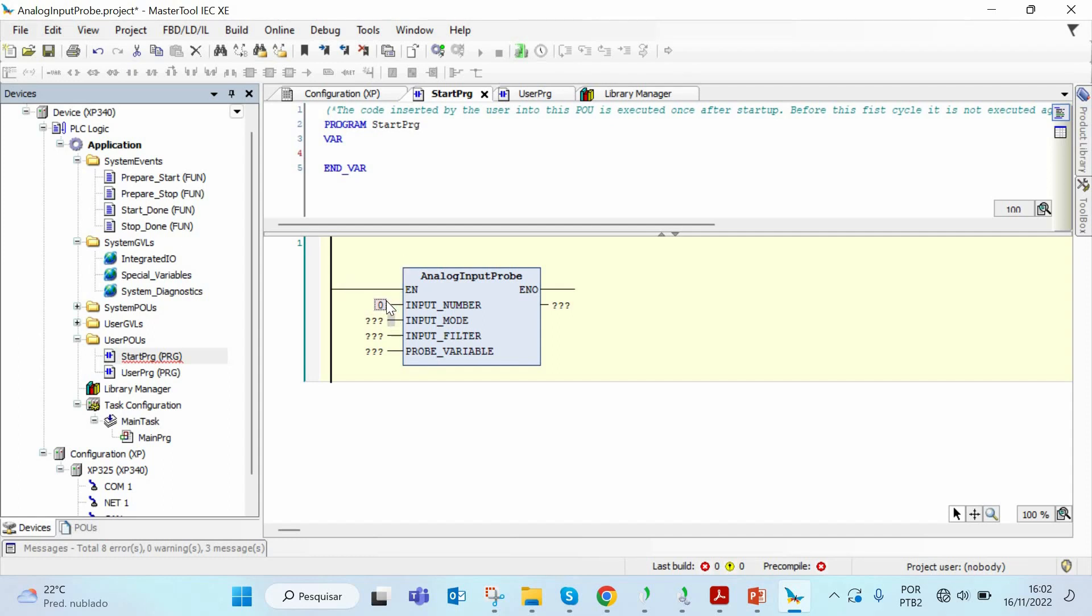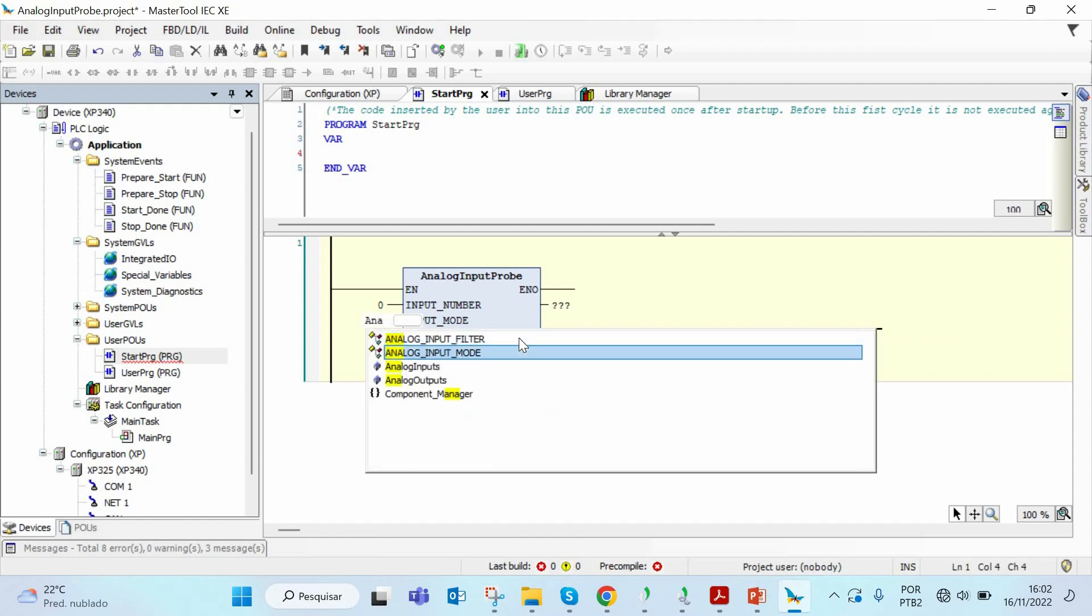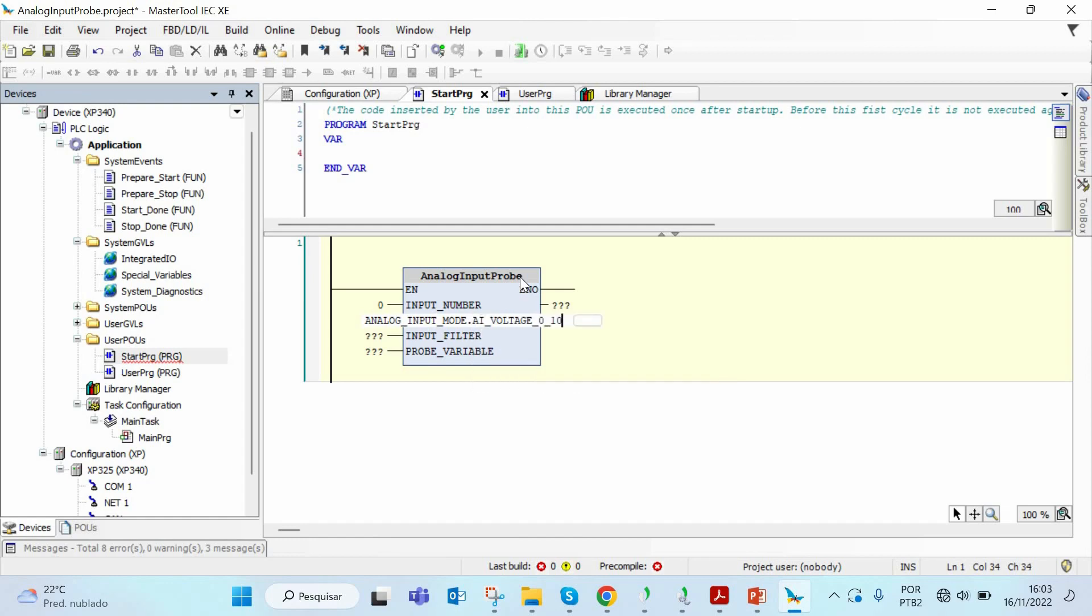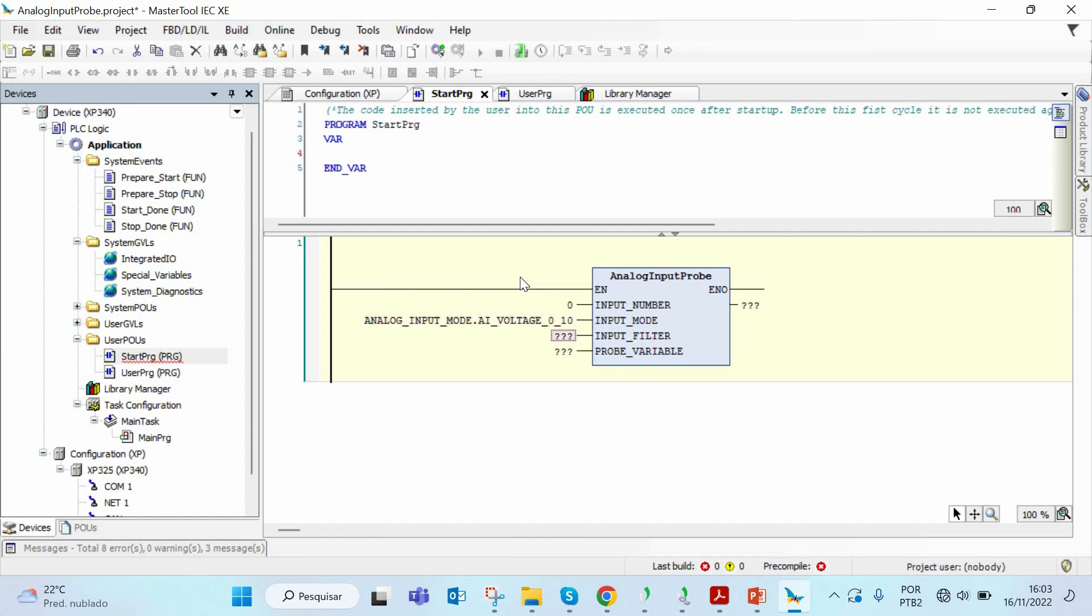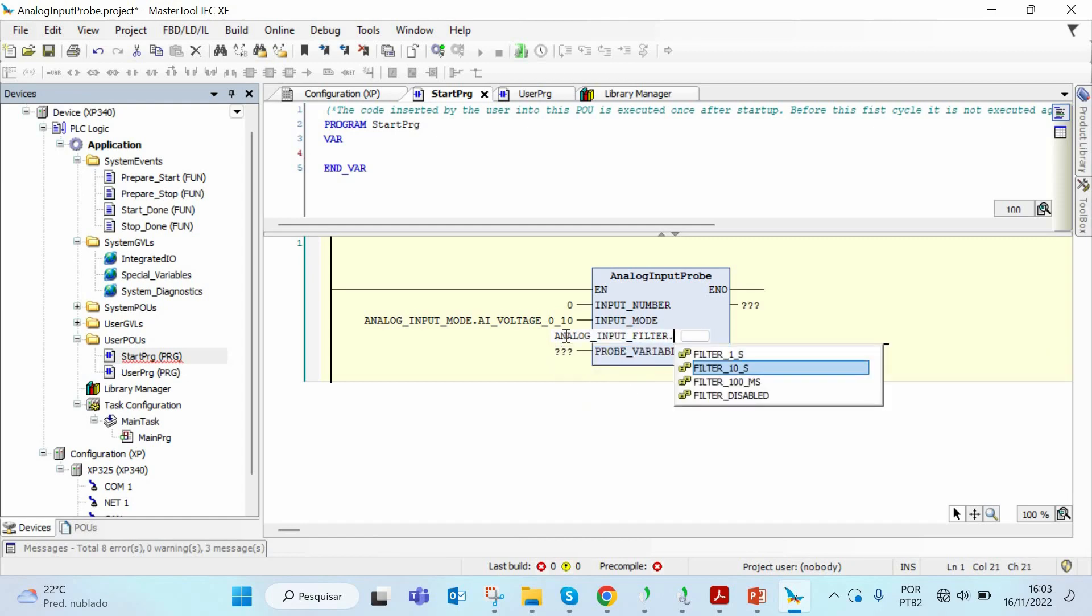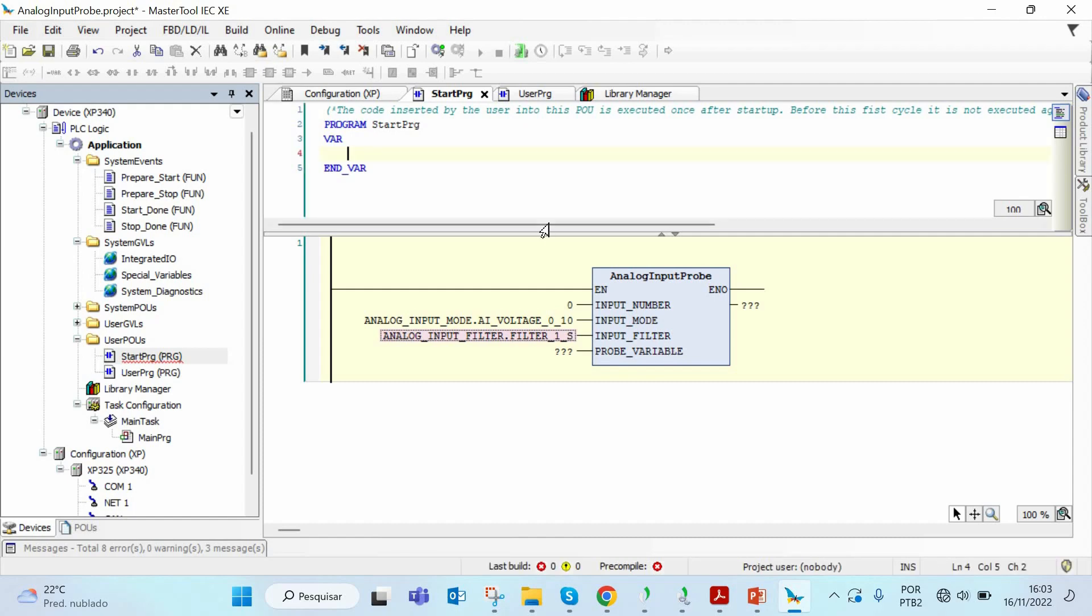Input mode is the type of the instrument that is connected on that pin, if it is voltage or current mode. We have to call by the struct analog input mode dot, in this case it will be voltage 0 to 10 volts. If we are going to use a filter on this analog input, we can select it here. I will call the struct analog input filter dot, I will select a one second filter. This probe variable is a pointer to an integer. You have to first declare a variable which will receive 0 to 3000, that is the value of the analog inputs on Nexto Xpress. So if it's zero volts, the value of the variable is zero. If it's 10 volts, the value of the variable is 3000.